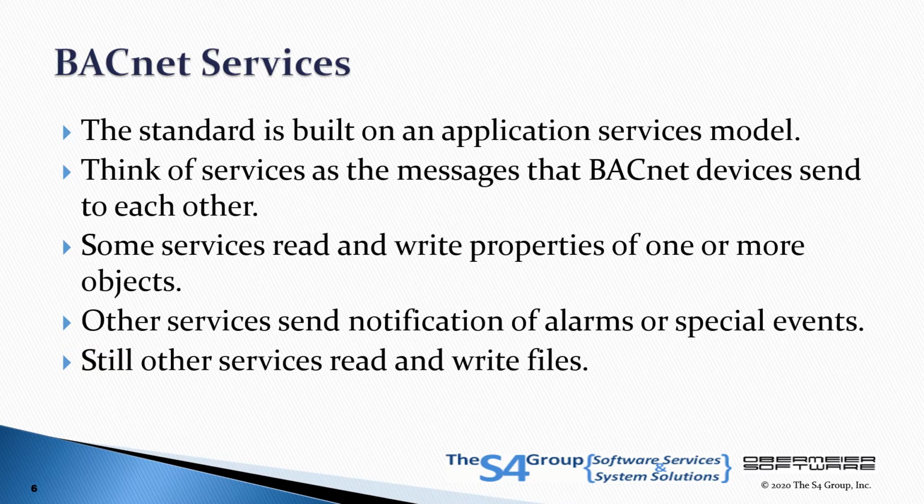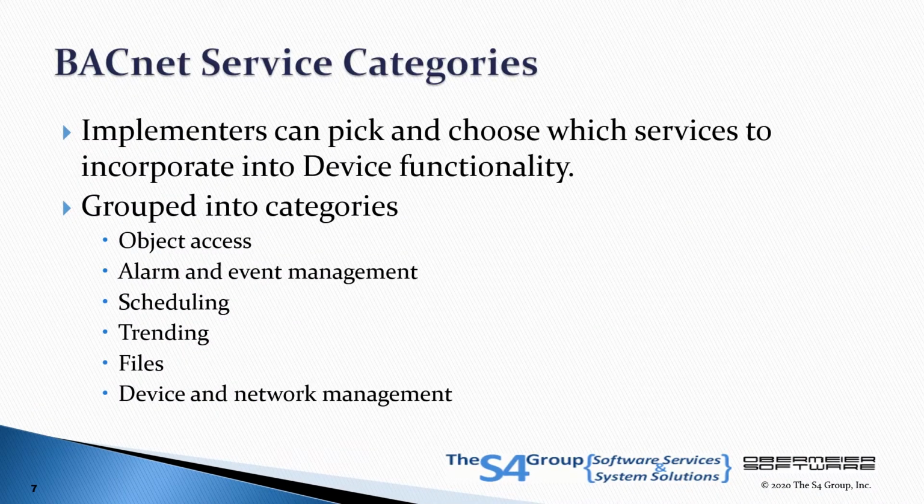BACnet services read and write properties of the objects hosted in devices. Status updates for objects are sent as notifications and events. Combined, the objects, properties, and services form the personality of a BACnet device. Services are grouped into categories to make it easier to describe the functionality provided by a service.